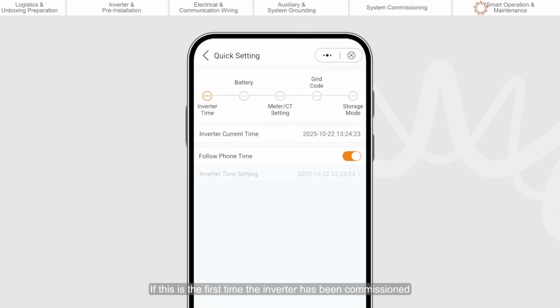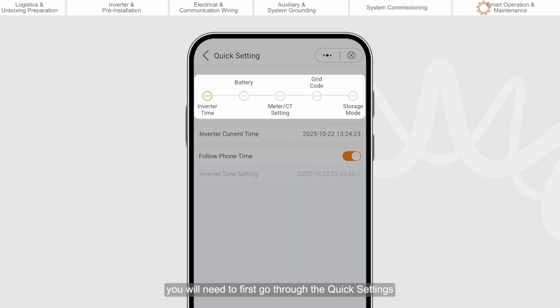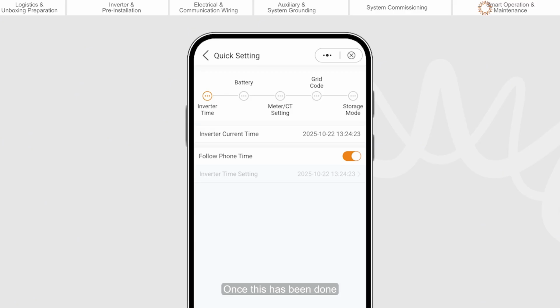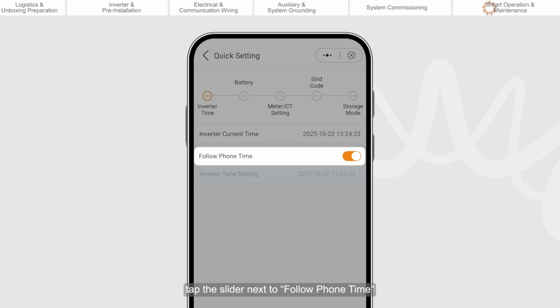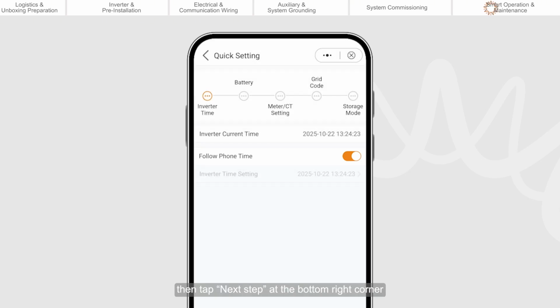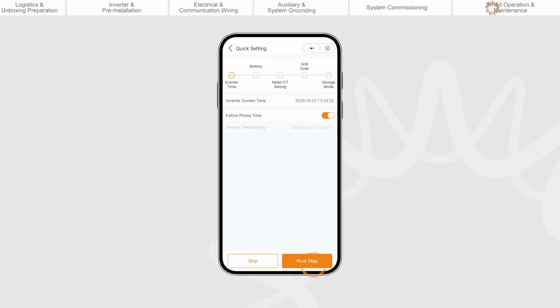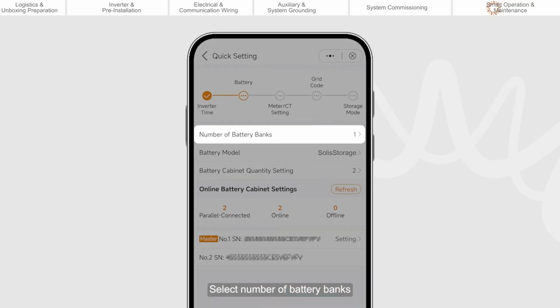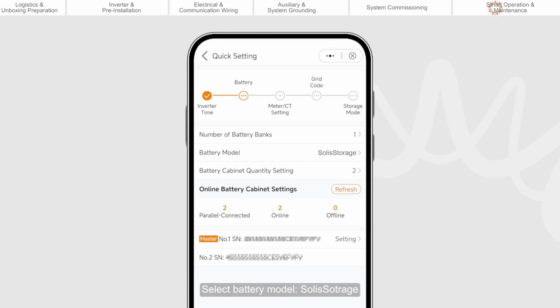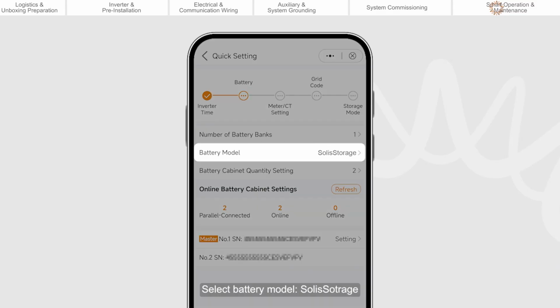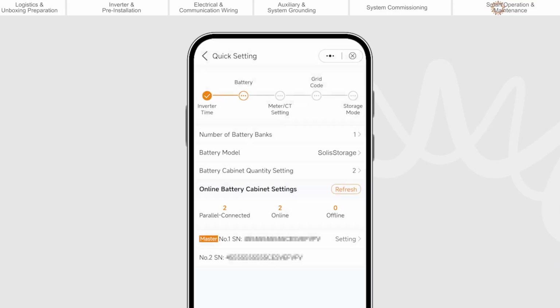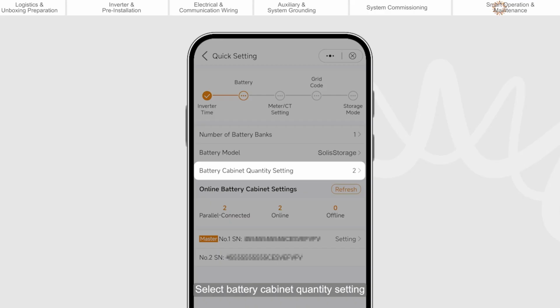If this is the first time the inverter has been commissioned, you will need to first go through the quick settings. Once this has been done, these settings can be changed later. Set inverter time and date. Tap the slider next to follow phone time, then tap Next Step at the bottom right corner. Select number of battery banks. Select battery model, SolisStorage. Select battery cabinet quantity setting.